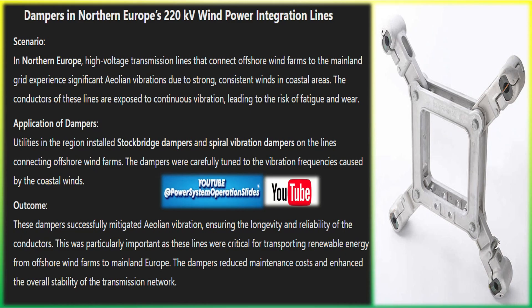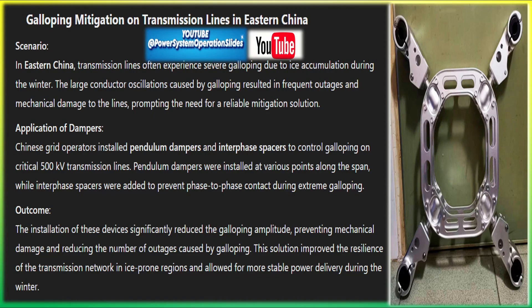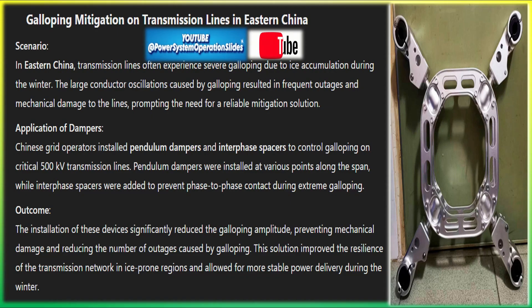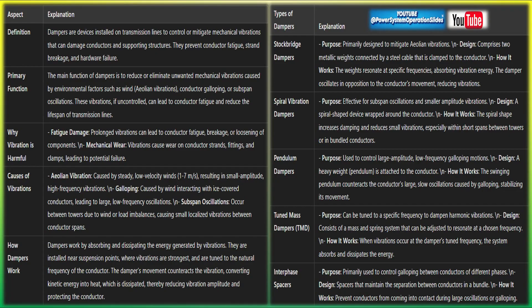Galloping control in the Netherlands' 380 kV lines used interphase spacers and tuned mass dampers to prevent faults and stress from winter galloping. In high-wind areas in New Zealand, Stockbridge dampers reduced Aeolian vibrations, extending the lifespan of transmission systems. In Northern Europe's 220 kV wind power integration lines, dampers mitigated coastal wind-induced vibrations, ensuring conductor longevity and reducing maintenance costs. In eastern China, pendulum dampers and interphase spacers controlled ice-induced galloping, reducing outages and mechanical damage. These examples highlight how dampers solve vibration issues, enhancing the reliability and longevity of power transmission systems worldwide.